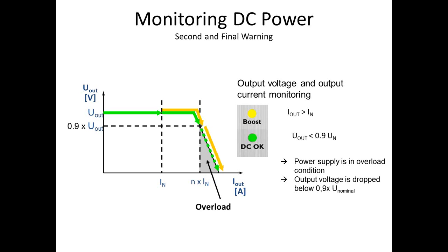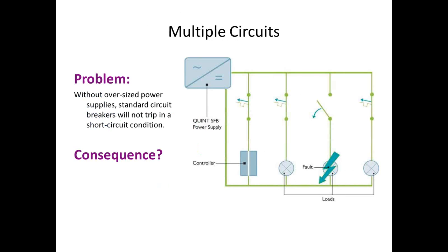If the DC bus continues to draw more current beyond the power boost rating, the voltage will start to drop. If the voltage drops 10% of the adjusted value, the second and final warning is sent to the control system. Please know that at this point, the control system could still be running. However, any further current demand will bring down the system. In this area of concern, the power supply characteristic is known as overload.